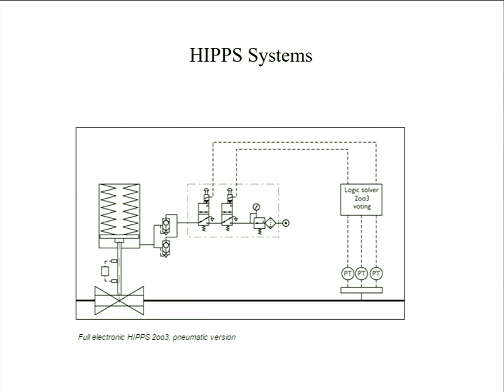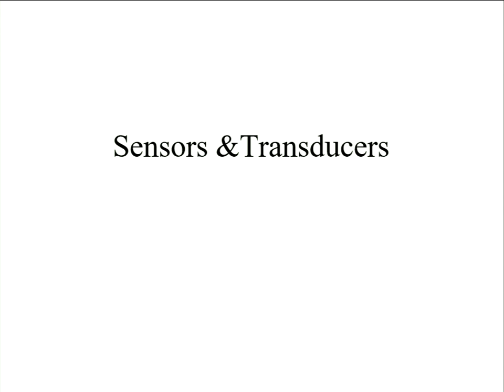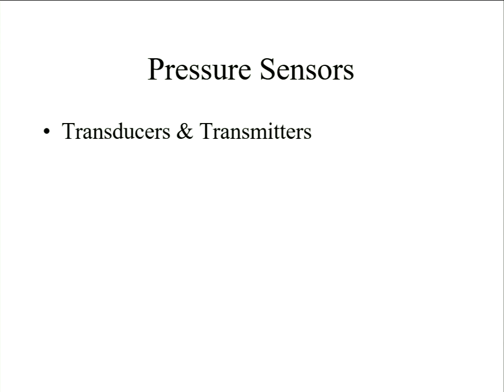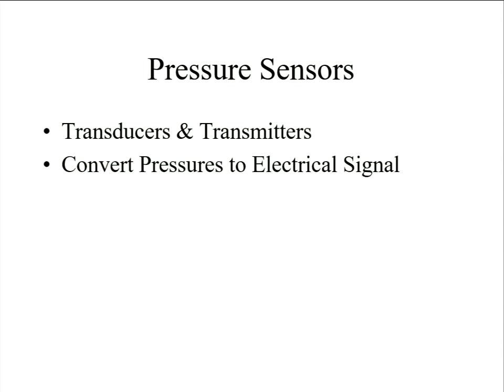So I think the subtlety between the two, typically transducers, a small device is just producing millivolt outputs, designed for small size, small cost. So you might find them out in local districts if they want to monitor pressure across districts on a small logger type device. It'll only deal with a short distance. Can be prone to a bit of interference, so you've got to do a bit of electromagnetic shielding. You need a regulated supply, and then you build that into a system through some components. I think there's a slide that shows a picture of a typical one.